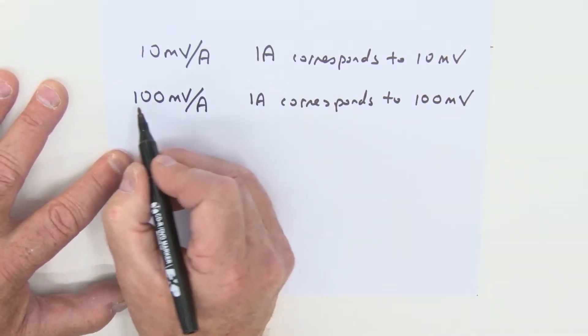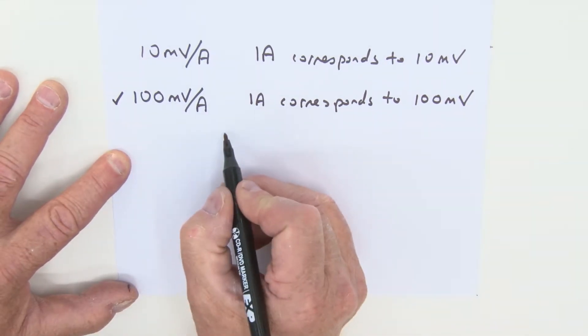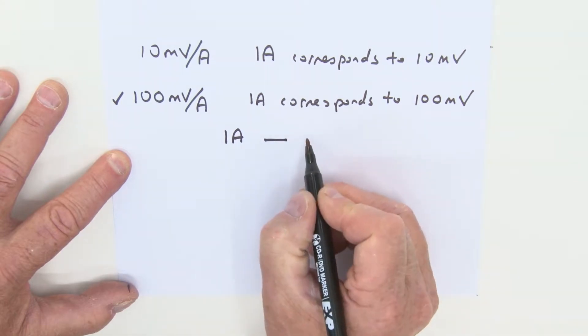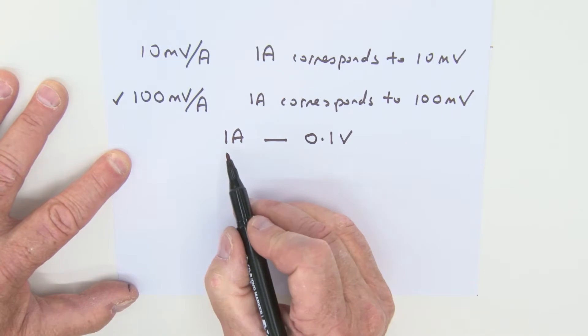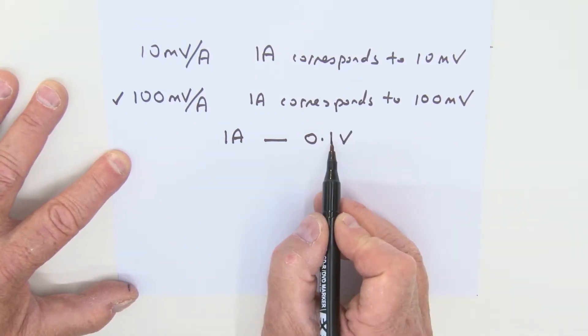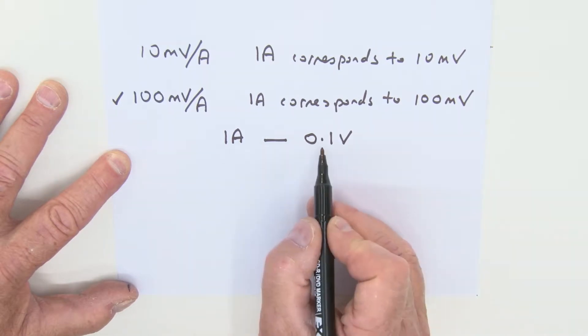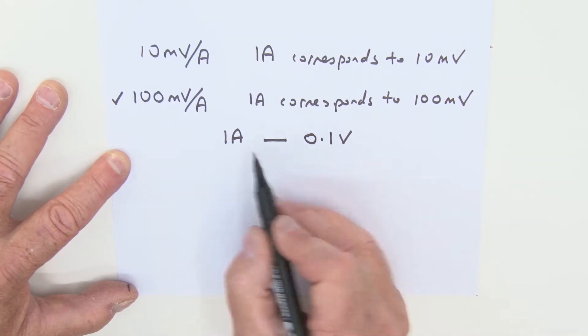So we're going to use this particular setting here. So in summary, what that really means is that one amp corresponds to 0.1 volts. There isn't a one to one ratio there. It is actually a 10 to one ratio. One amp corresponding to 0.1 volts. And we'll make note of that.